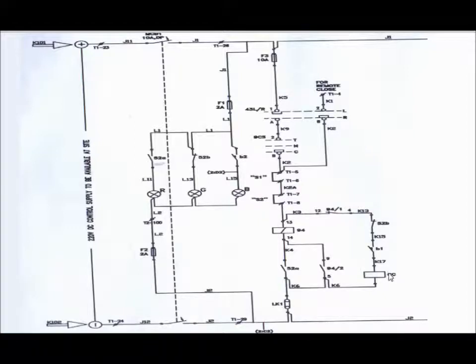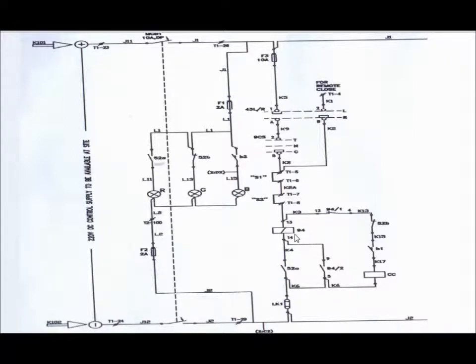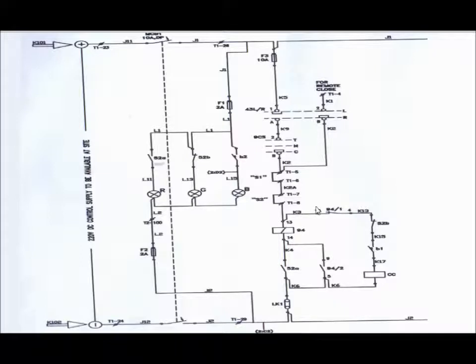CC is the closing coil of the circuit breaker. 94 is the anti-pumping relay located at the circuit breaker. 94/1 is the auxiliary NC contact of the anti-pumping relay, and 94/2 is the auxiliary NO contact of the anti-pumping relay. 52A is the auxiliary NO contact of the circuit breaker, and 52B is the auxiliary NC contact. B1 is the spring charge contact — if the spring is in charged position, this must be in NC (make) position.